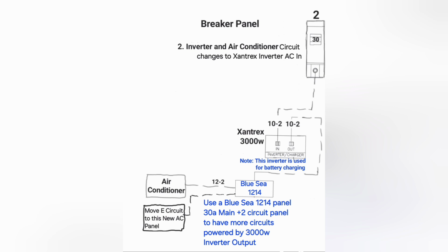So to do that, I need to add a sub panel for the Xantrex AC output, with a 30 amp breaker, and then that 30 amp breaker will feed two more breakers or circuits that I add to that 3000 watt inverter output.